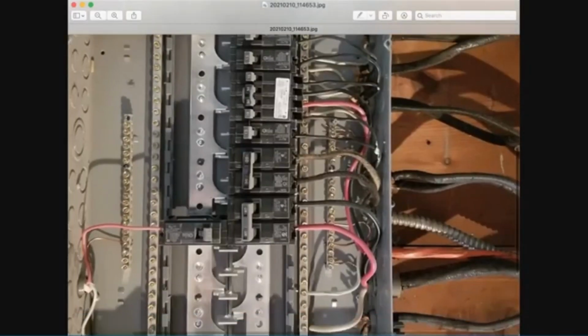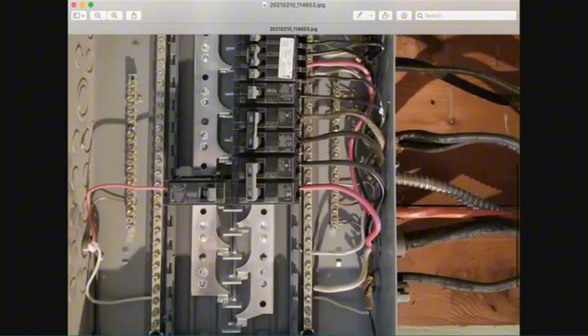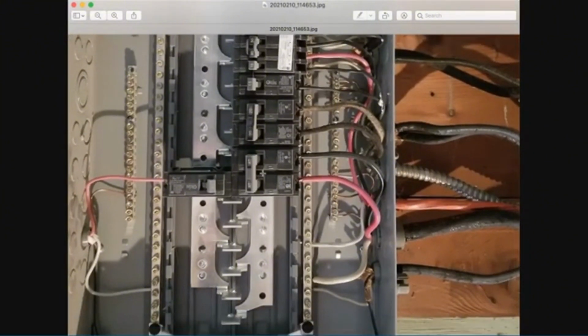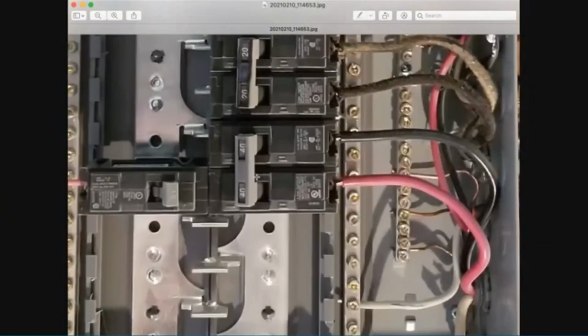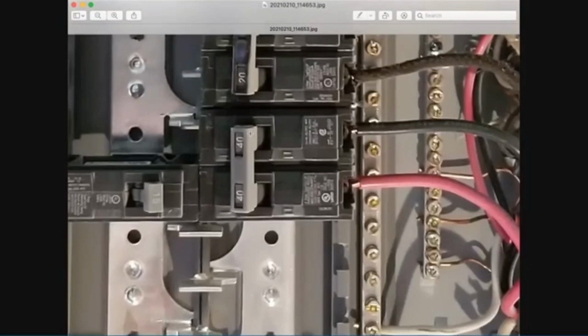You can see on some of these breakers we can actually read the amperage. For example, let's look at this one - this is a 40 amp circuit breaker. What would I need to use a 40 amp circuit breaker for? The stove. What wire gauge does a 40 amp circuit breaker require? American wire gauge number 8.